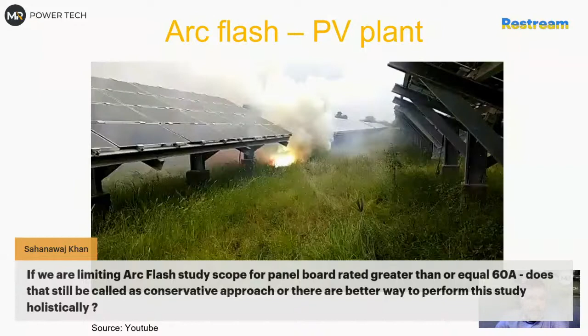And if you would like to go by IEEE or NFPA, then we have to include everything which is above 2000 amp short circuit current level and above 208 volts, which means sometimes quite a lot of equipment in a plant. But to know all the data, you have to run a short circuit current study. So generally, you have to model everything at this point. That's why, as I explained, we always start with 63 amp as a reasonable approach.